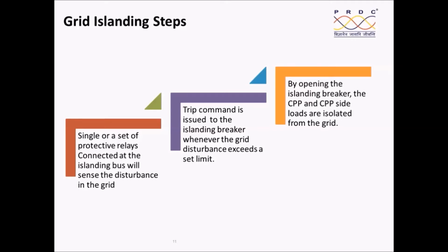Therefore, this is very important. How to give the trip command to the islanding breaker? There are set parameters, and when those set parameters are violated, then the trip command is given to the islanding breaker. Then after the islanding breaker is opened, on the CPP side, loads are isolated from the grid. Assume that there is excess load, then some of the loads have to be isolated from the grid. That is also equally important.